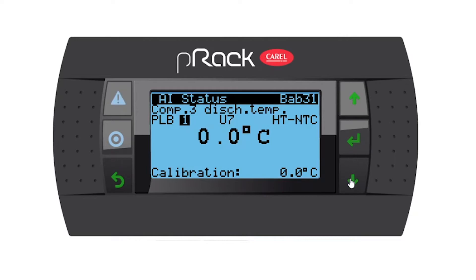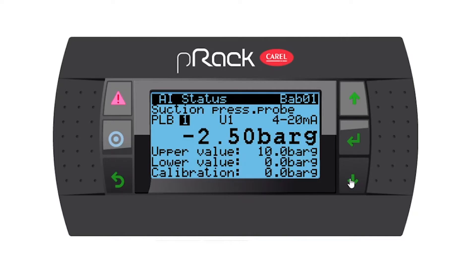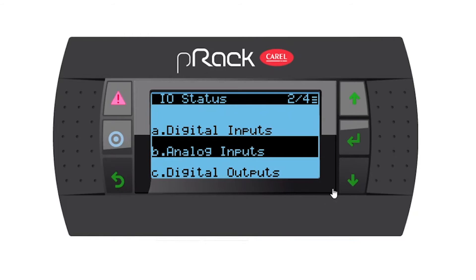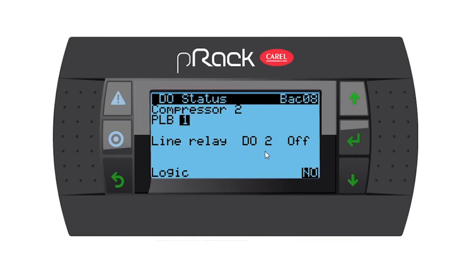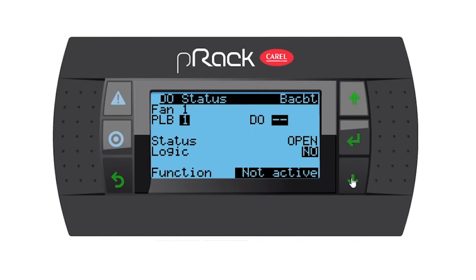Going down — do you have a compressor one oil temperature, compressor two oil, compressor three oil? These are all options. Now we're back at the beginning, so we're done with analog inputs. Going back, we'll now go to digital outputs. Compressor one I'm going to assign to DO1 with normally open logic. Compressor two is going to be two with normally open. Remember to use your wiring diagram. Let's go down to number three — I'll assign it to three, normally open.